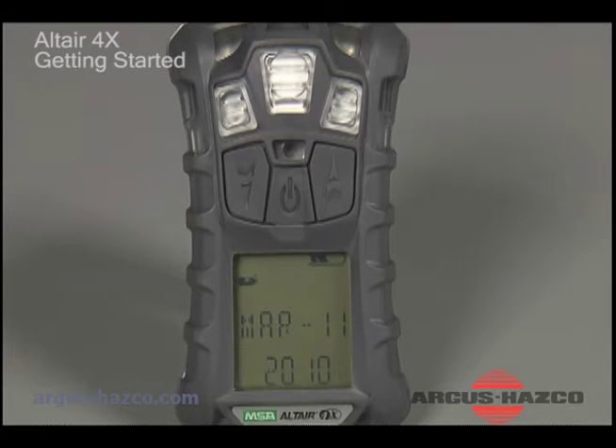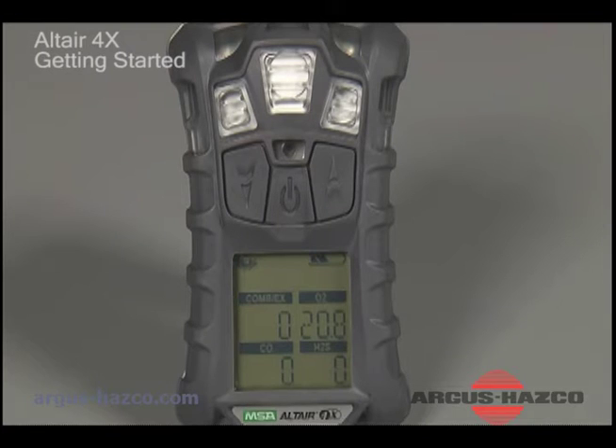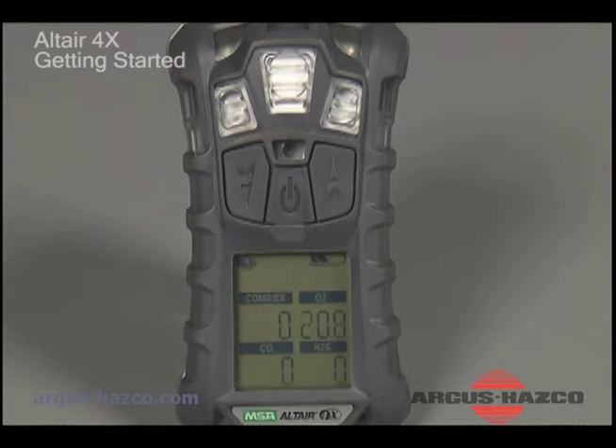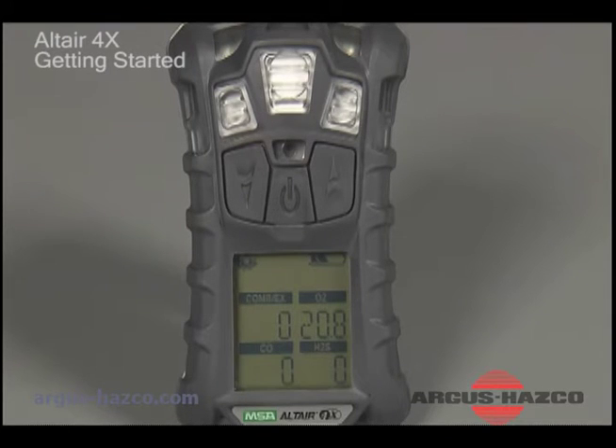The last startup sequence page alternates between FAS and current gas readings as a prompt, asking users if Fresh Air Setup should be performed. This page is optional and can be turned off through MSA-Link software.